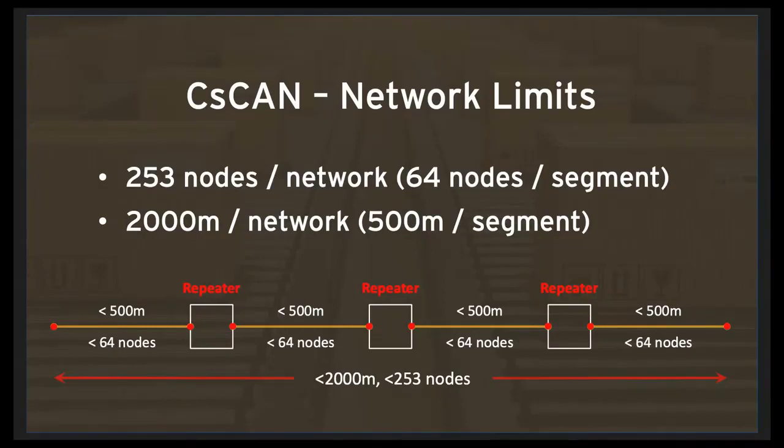Again, I want to stress that most applications are far less than 500 meters or far less than 64 nodes, so you don't need a repeater. But when we're talking about network limits, we need to talk about repeaters. One other thing I will mention, and that is not all repeaters are created equal.